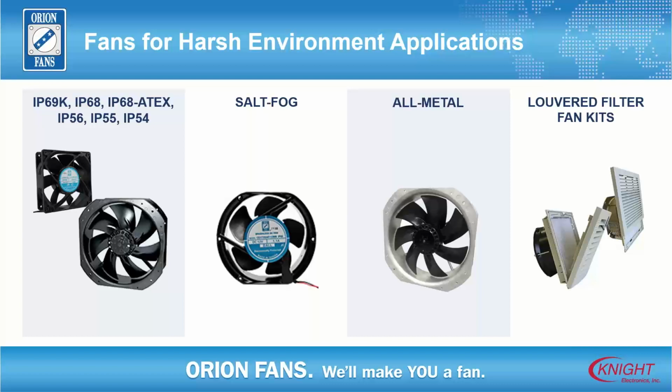So people want an IP68 cabinet. Well, realistically, that's absolutely not physically possible because you've poked a hole in it, and when you have a hole in it, water can get in. Our fan will live in that water getting in, but your cabinet's no longer going to be IP. It wouldn't be IP68 rated because it's got a hole.